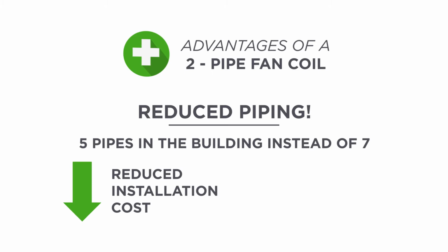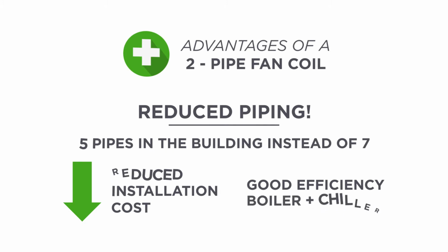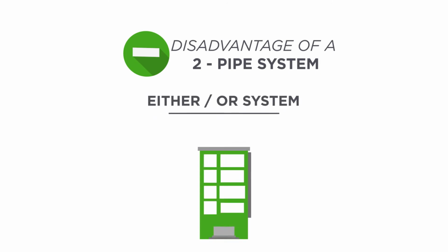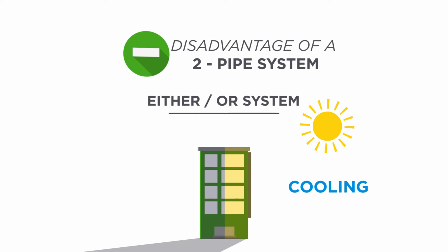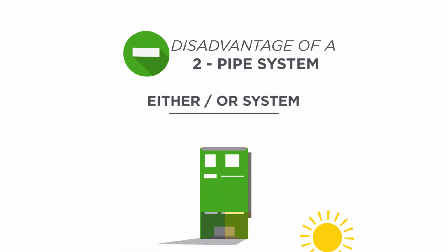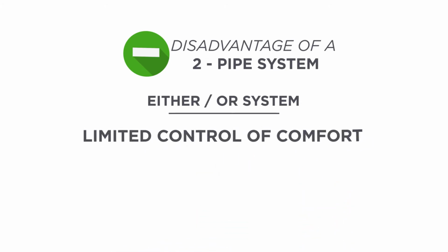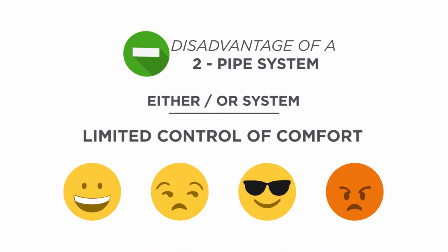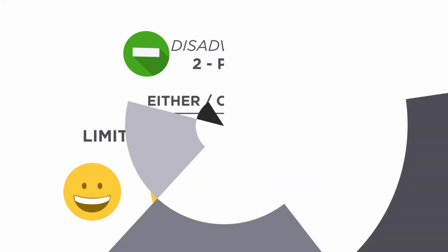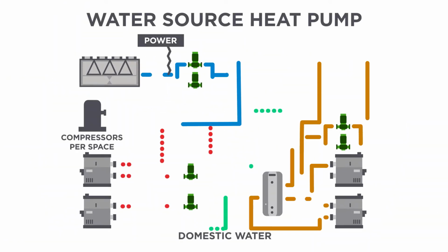The building also still has good efficiency since the 2-pipe hydronic system still has a central boiler and chiller. The main disadvantage with the 2-pipe system is that it is an either-or system, which means all occupants in the building have to have either heating or cooling. So if the southern exposure of the building in September requires cooling, but the northern exposure still requires heating, there's a loss of comfort. Guests or tenants now have a very limited control over their comfort. You can't make everyone happy with a 2-pipe system. Another system choice available is the water source heat pump.